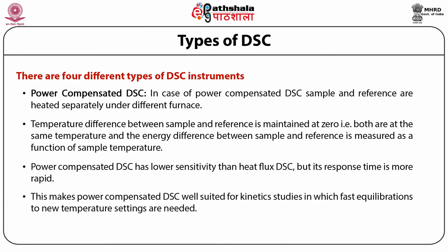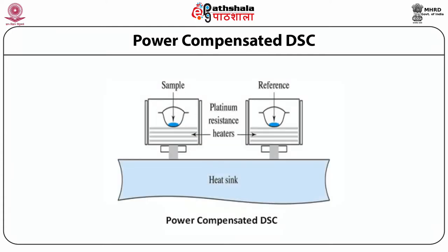Power compensated DSC instruments also have higher resolution than heat flux DSC. The calibration constant in power compensated DSC, which converts peak area into joules, is an electrical conversion factor. In the basic diagram of power compensated DSC, the sample is shown in the left window and the reference in the right window. The horizontal lines under the sample and reference are designated platinum resistance heaters, connected to a heat sink.